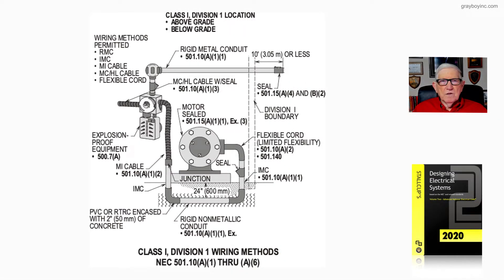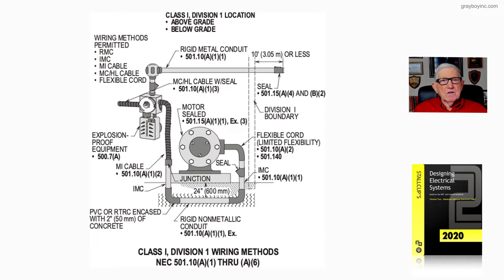Let's take a look at figure 21-21 out of Stallcup's Designing Electrical Systems book, volume 2. This deals with Class 1, Division 1 installing wiring methods above grade and below grade. To the left of the illustration, we have wiring methods permitted, like rigid metal conduit, IMC, MI cable, MCHL cable, flexible cord — some of those that are used the most.